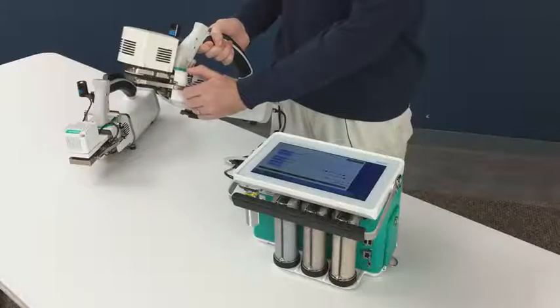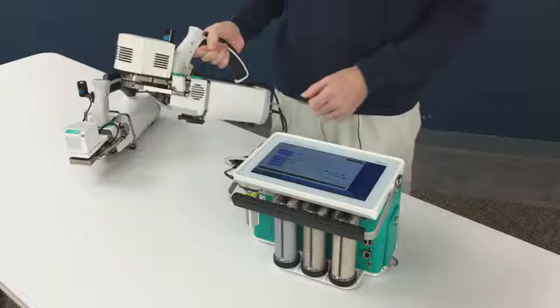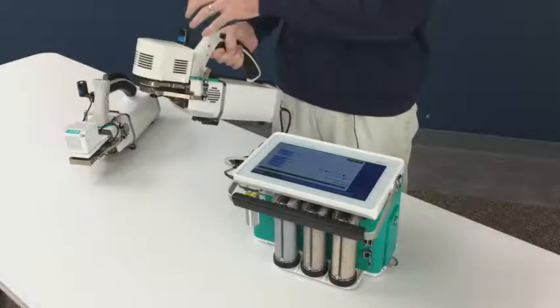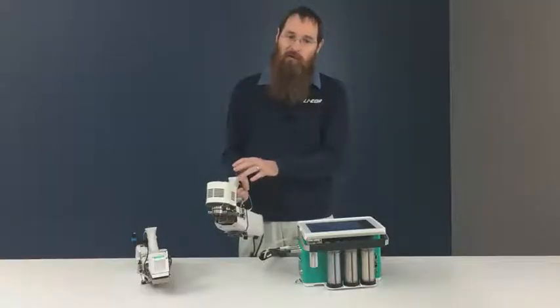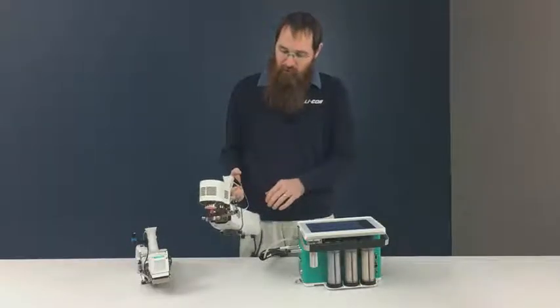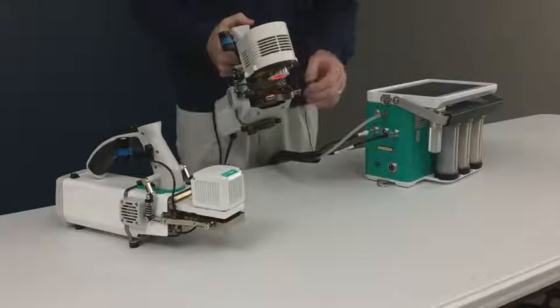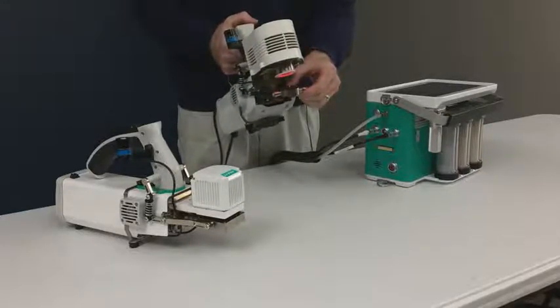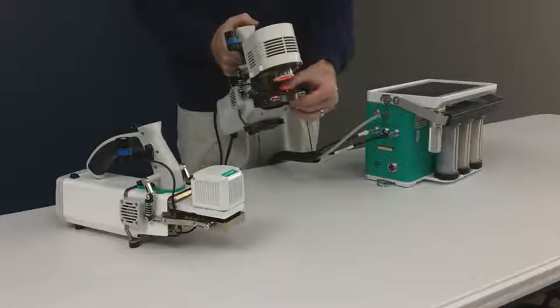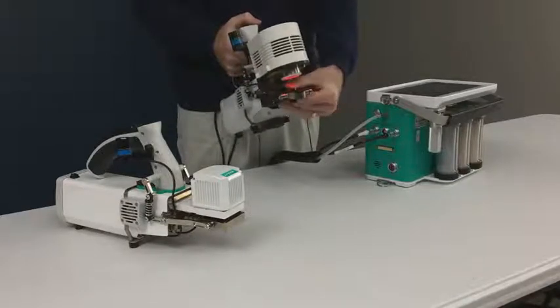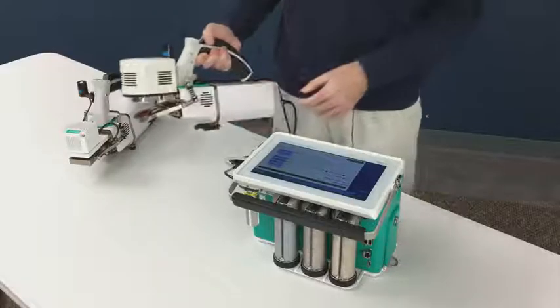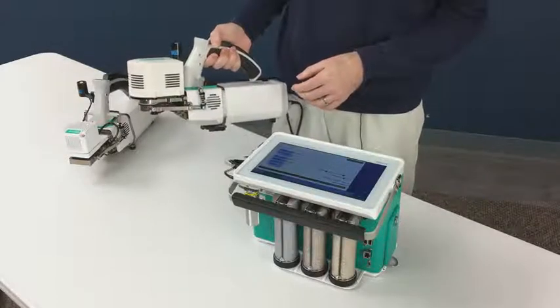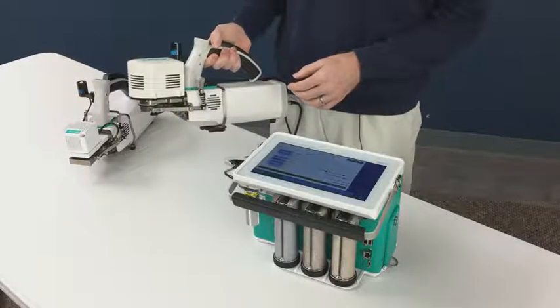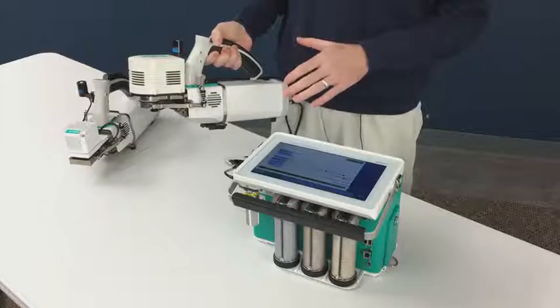Tension on the chamber closure is set by springs, so there's no chamber tension adjustment for the user to make. The chamber bottom more or less floats in a few different axes—I can twist this thing around, and this allows for an even clamping pressure. The chamber bottom approaches the chamber top parallel to each other.